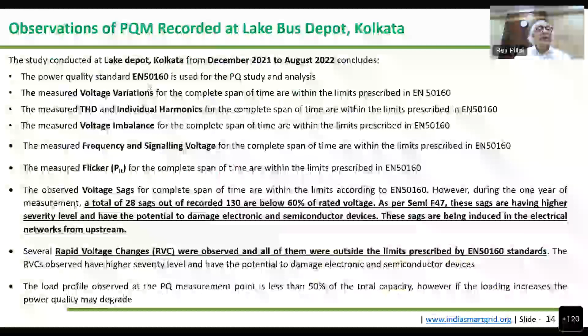And key findings here again: the actual meter reading we have been capturing in real time in a server in the ISGF office. We had some communication trouble in the beginning, so from December 21 to August 22 we have complete data without any interruption. We compared this with the EN 50160 standards: voltage variation, total harmonic distortion, individual harmonics, voltage imbalance, frequency, signaling, flicker. All of these are within the prescribed limits of the standard.